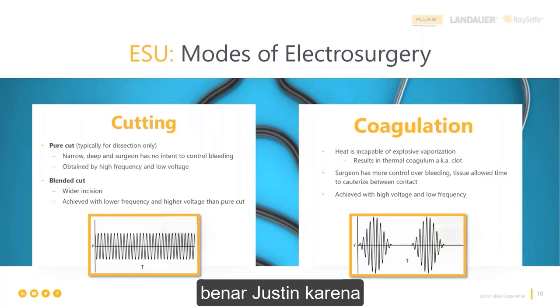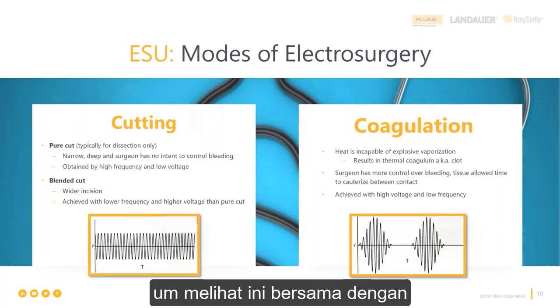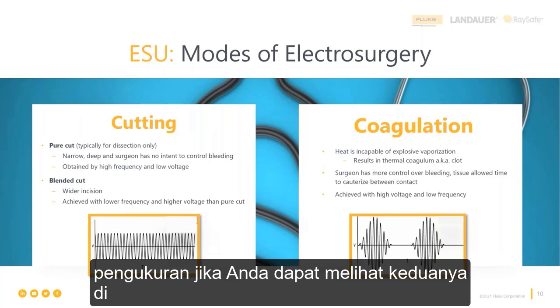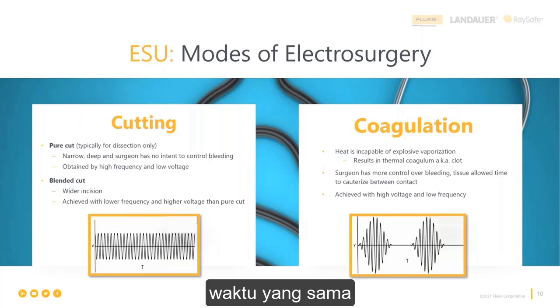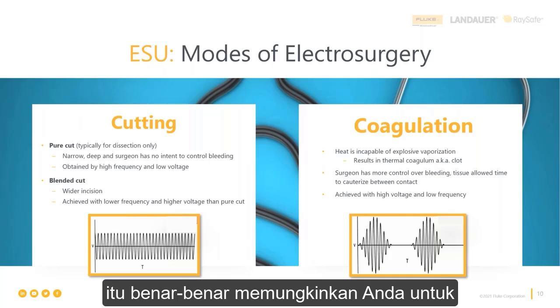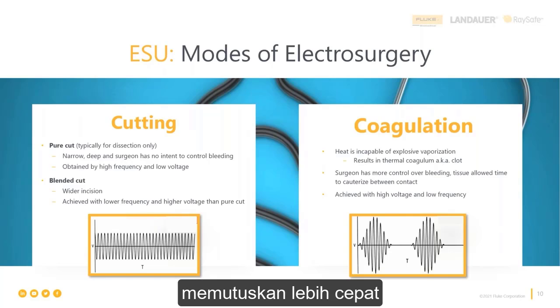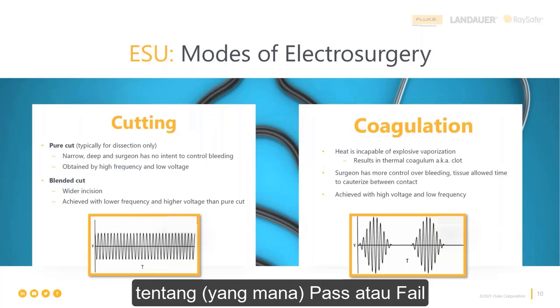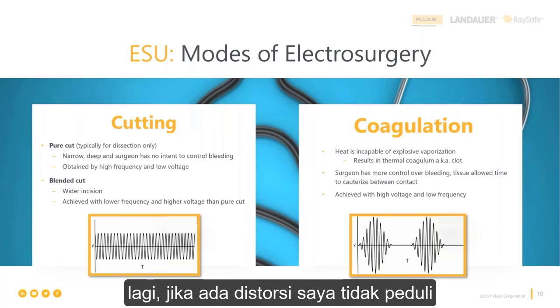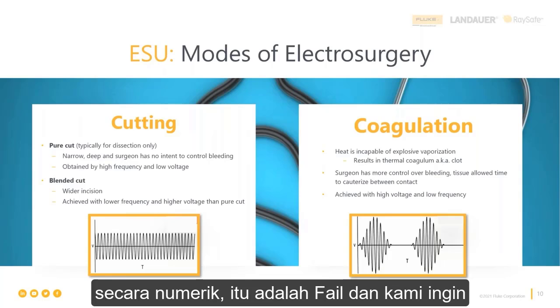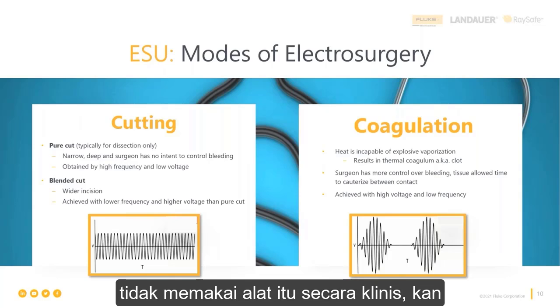But you're very right, Justin, because viewing these along with the measurement, while you're making the measurement, if you can see both at the same time, it really allows you to decide quicker about a pass or a fail. Again, if there's distortion, I don't care what the measurement shows numerically, it's a fail, and we want to remove that from clinical use, right? Yes, sir.